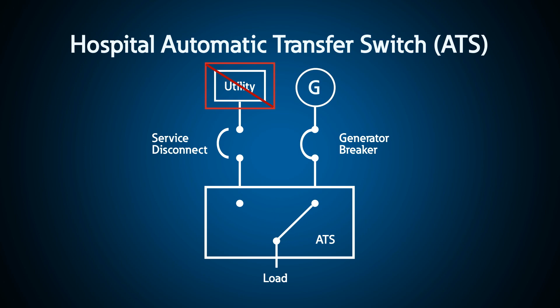The essential electrical system loads are connected to the load terminals of a transfer switch. In healthcare applications, bypass isolation transfer switches are often used because you can do maintenance on half of the transfer switch while still having a fully functional transfer switch to protect the loads.